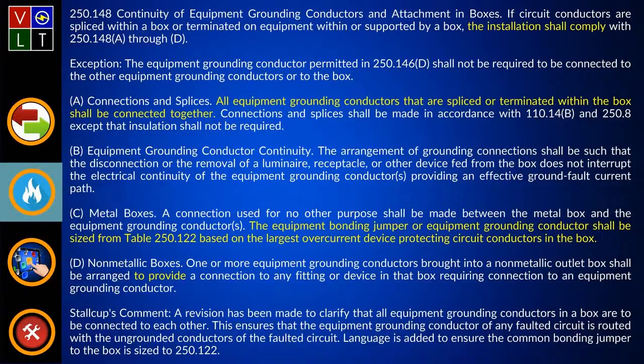And then they also added language here, and where you have metal boxes, they tell you when you're sizing that equipment bonding jumper or equipment grounding conductor, what table do you use? Table 250.122, based on the overcurrent protection devices, or should I say the largest overcurrent protection device, or the largest ungrounded conductor usually.